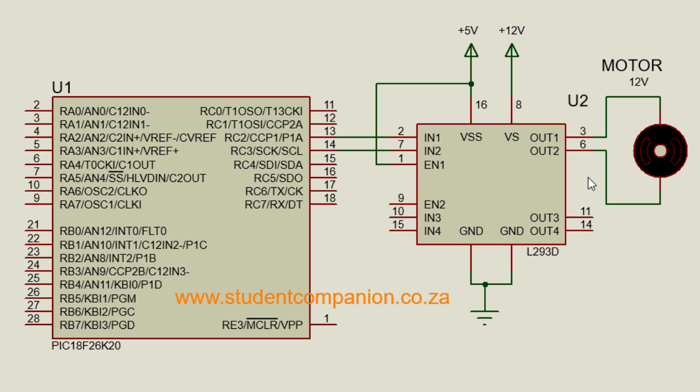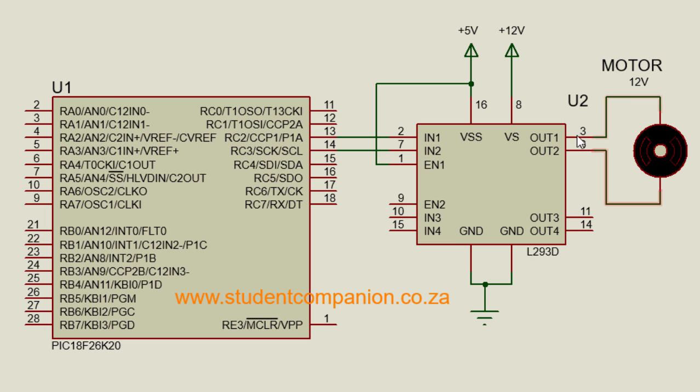The second problem, if we connect a resistor, it's going to drop excess energy as heat. So this will be a huge loss. And lastly, as the motor requires more current, resistors with higher power rating are required to drop the excess energy. So this is clear that you cannot use a simple resistor to change the speed of a motor.